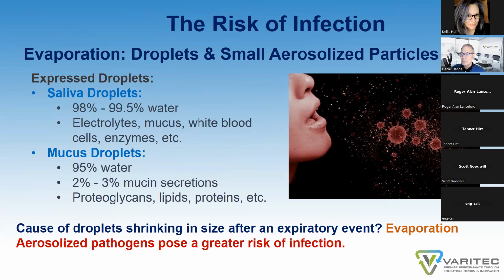So they can stay in a room for a considerable amount of time. Well, the reason why humidity is an important factor is because droplets released by an infected agent, whether they're saliva droplets or mucus droplets, are predominantly water. And if you have a dry environment, those droplets will evaporate within 1 to 2 to 3 seconds, releasing desiccated aerosolized pathogens into the environment where they are more likely to free float and become an increased risk of infection to those in the environment that are beyond the social distancing guidelines.